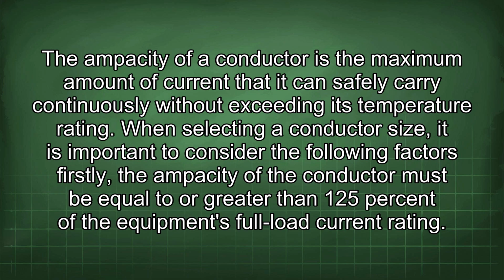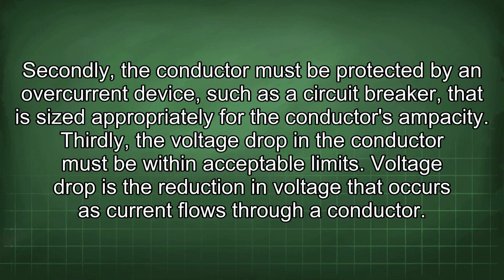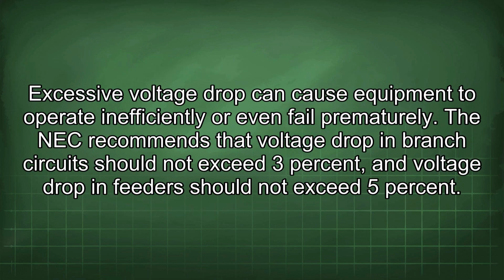Firstly, the ampacity of the conductor must be equal to or greater than 125% of the equipment's full load current rating. Secondly, the conductor must be protected by an overcurrent device, such as a circuit breaker, that is sized appropriately for the conductor's ampacity. Thirdly, the voltage drop in the conductor must be within acceptable limits. Voltage drop is the reduction in voltage that occurs as current flows through a conductor. Excessive voltage drop can cause equipment to operate inefficiently or even fail prematurely.